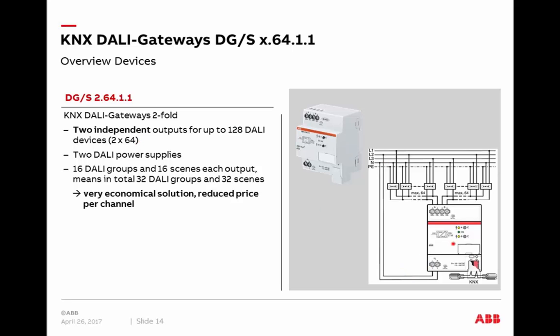In the two-fold component, there are two independent DALI power supplies — one per channel. In case of any malfunction on one channel, such as a short circuit or missing power, the second output is independently supplied, so there is no total component failure. Each output supports 16 DALI groups and 16 scenes — 32 groups and 32 scenes in total. From a commercial perspective, the price per channel is reduced, making it a very economical solution if you can use a two-channel device to connect up to 128 DALI ballasts. All functions are available for each channel with no disadvantages.